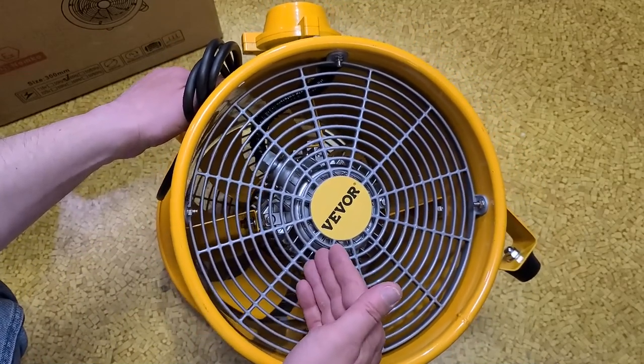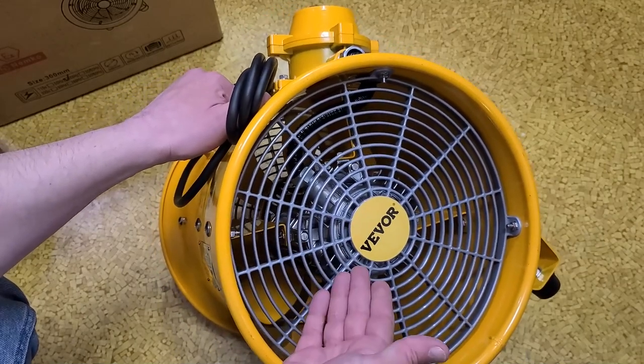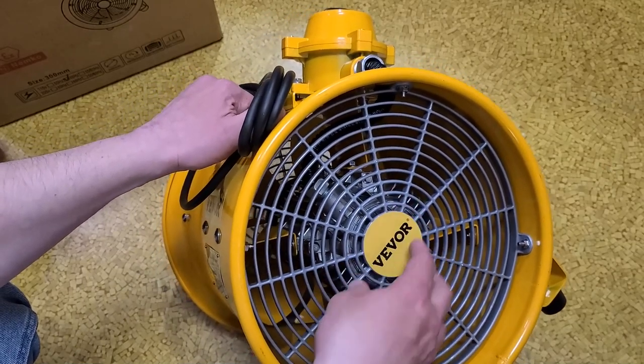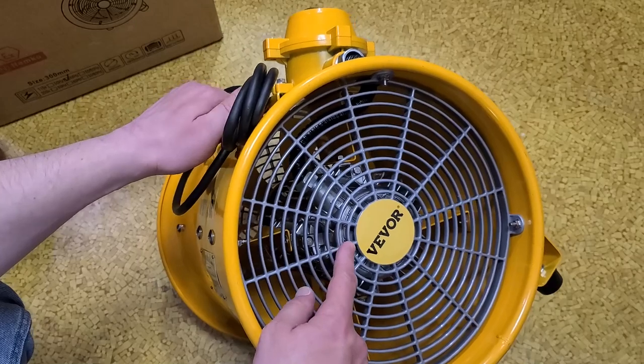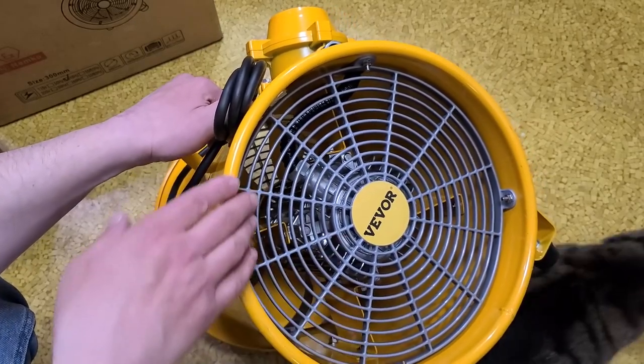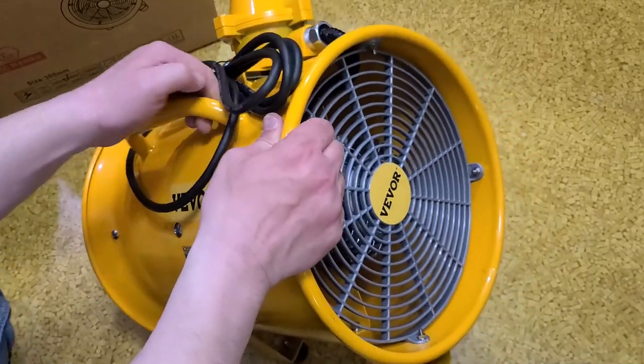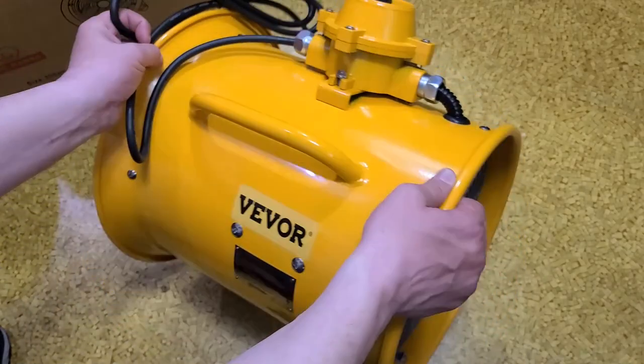It has a super heavy-duty case with a pretty thick wall — fully sealed motor, totally enclosed cast housing with fins. This isn't a self-cooled motor in the traditional sense because it's a fan, but the motor doesn't have a separate fan on the back. The capacitor is integrated inside the back of the motor and isn't exposed, which prevents any kind of static discharges.